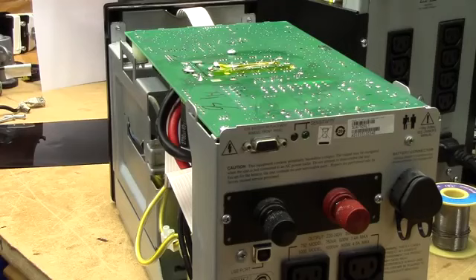The reason it's possible to do this modification so easily on these units has to do with the way the feedback system is designed on them, because there is no feedback from the actual output of the switching transistors, but rather the entire inverter is included in the feedback network. So as long as you have the DC 24 volts, or at least the UPS thinks it has the DC 24 volts on the battery side, and there's 230 volts AC on the secondary, it'll keep going. Because all the regulation is done internally through that regulation loop, it has no reason to actually monitor anything else.